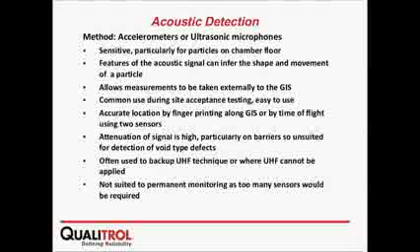It is not suitable for permanent monitoring as too many sensors would be required. So with acoustics, if you want to have good localization and do online monitoring, you need a lot of sensors. Imagine a big substation; it would be really not cost effective.